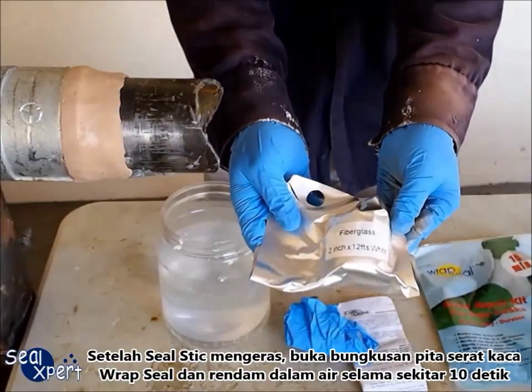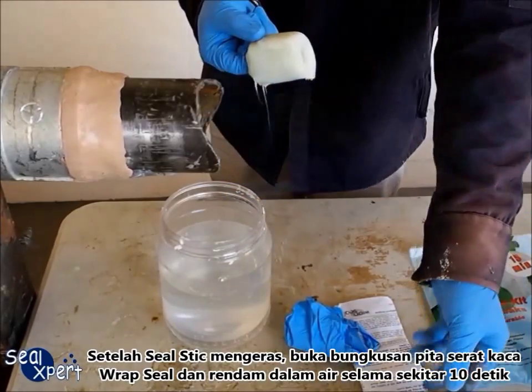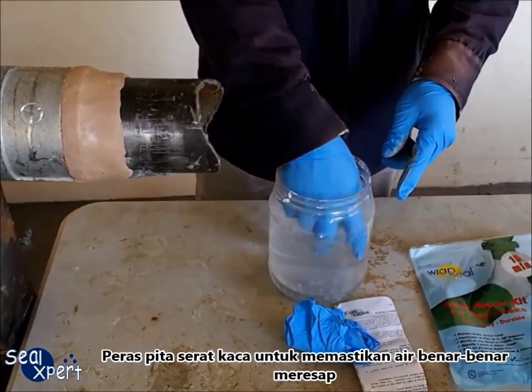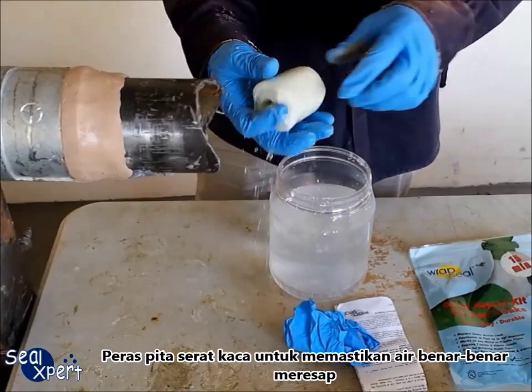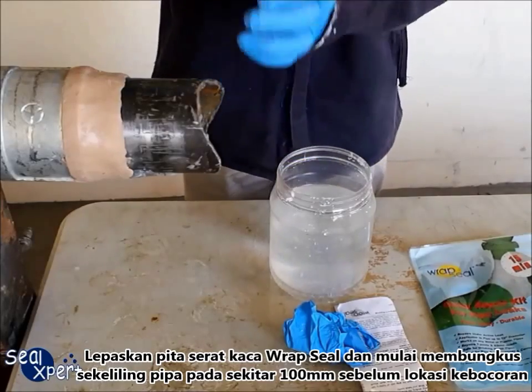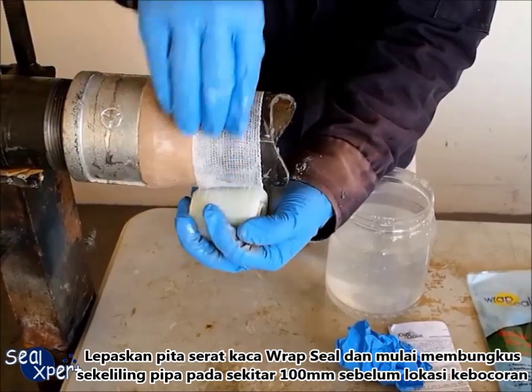After the Seal Stic is cured, open the pack of Wrap Seal fiberglass tape and soak in water for about 10 seconds, squeezing the fiberglass tape to ensure water is fully immersed. Remove the Wrap Seal fiberglass tape and start wrapping around the pipe at about 100mm before the leak location.